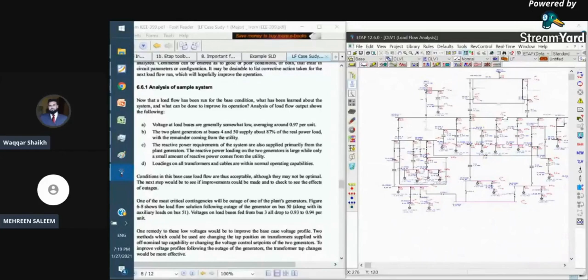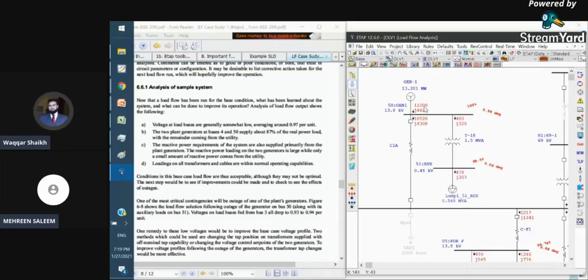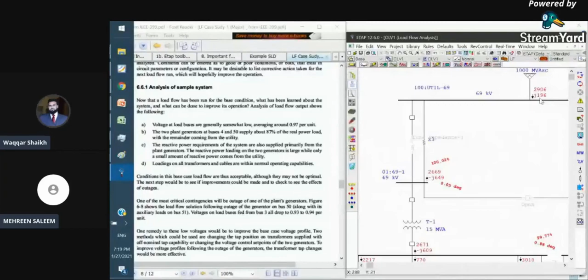For understanding this statement, you need to see what are the active and reactive power injections from the sources. Like we have Gen 1 supplying 1100 kilowatt as active power and 4628 kVAR as reactive power. So these are P and Qs from the generator into the network. Similarly, the utility is contributing 2906 kW active power and 1196 kVAR as reactive power. Okay, and similarly the third generator on the right side. So what he is saying, let us do this mathematics here.